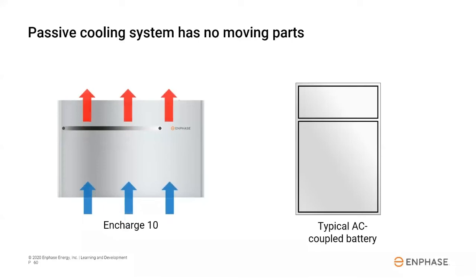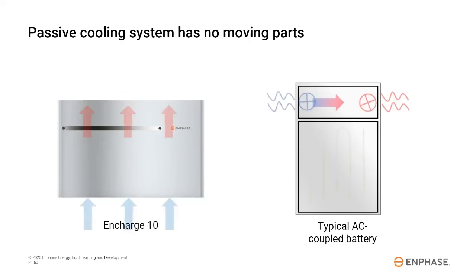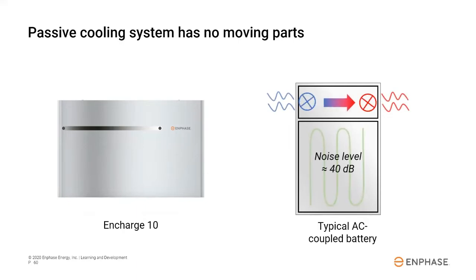Typical AC coupled battery systems use more common NMC chemistry, which has an inherently higher susceptibility to thermal runaway and fire. To ensure safe operation, they typically have active cooling systems with liquid coolant, pumps, and fans to enable rapid cooling when needed. These additional moving parts increase the number of fail points in each battery. The cooling system actually emits about 40 decibels of noise, similar to a large refrigerator. So locating the battery opposite a bedroom or other quiet space isn't ideal.